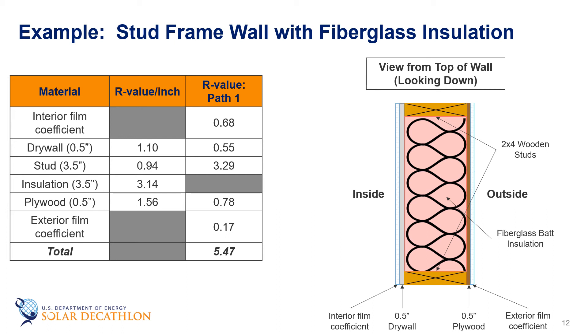For Path 1, starting with the interior film coefficient, just like the previous episode, we have R equals 0.68. Next is the drywall which has an R value of 1.10 per inch, so half-inch drywall is 0.55. The 2x4 stud is 3.5 inches in the direction of heat transfer, so at 0.94 per inch the R value is 3.29. The half-inch plywood has an R value of 1.56 per inch resulting in an R value of 0.78. And finally, the exterior film coefficient is 0.17. Adding these R values yields a total R value for Path 1 of 5.47.